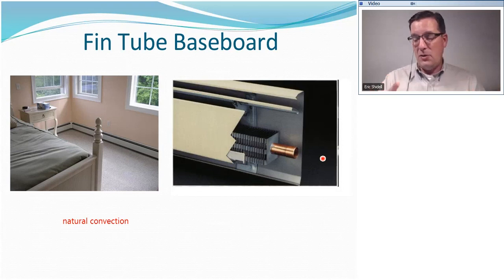You might be able to get away with trying to bend the fins a little bit to create some more tension in there to get them to grip on the tube a little more tightly. There's no guarantee that that's actually going to be effective. And the only real solution is to replace all of the baseboard elements if they're clicking. So that's a common complaint from folks. You know, their house may have been built in, say, 1974, and here it is in 2000-whatever, and they're clicking, and they're going to click.